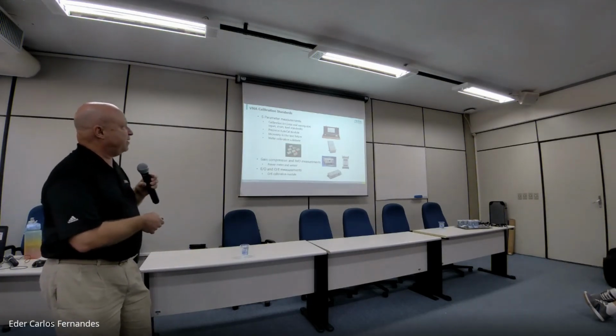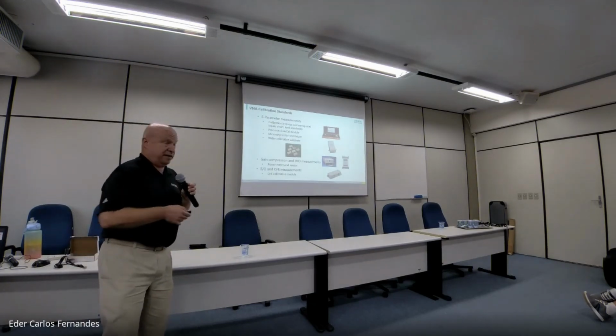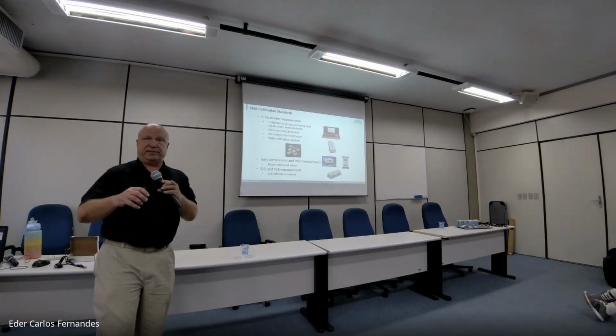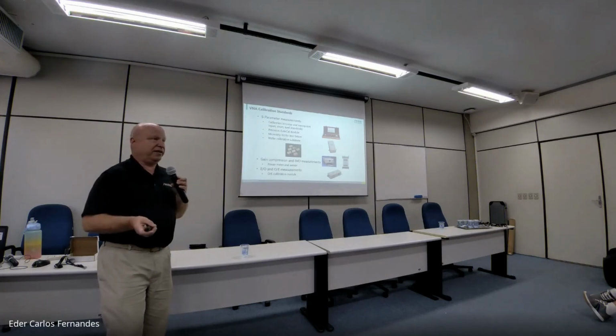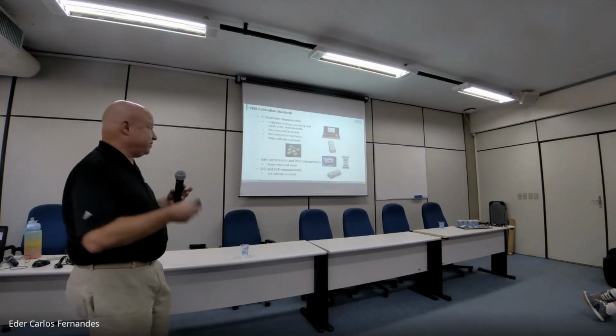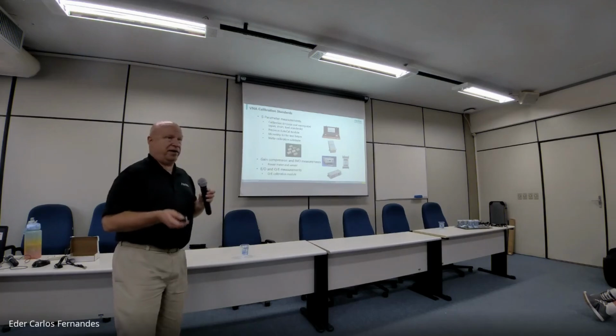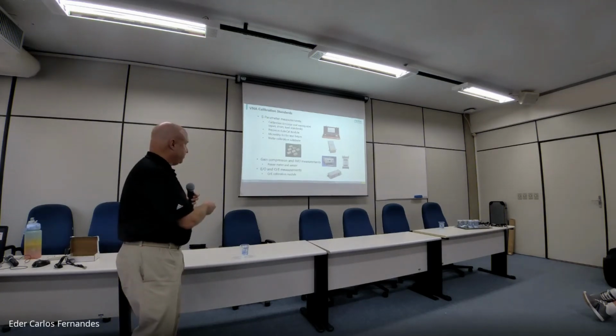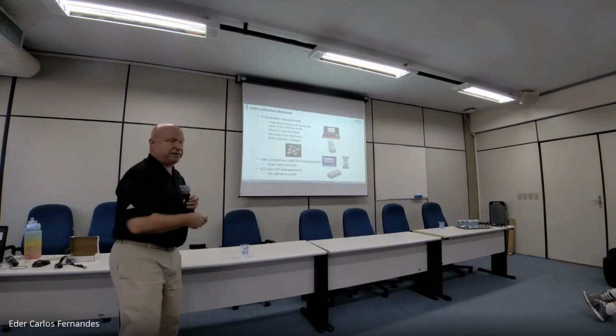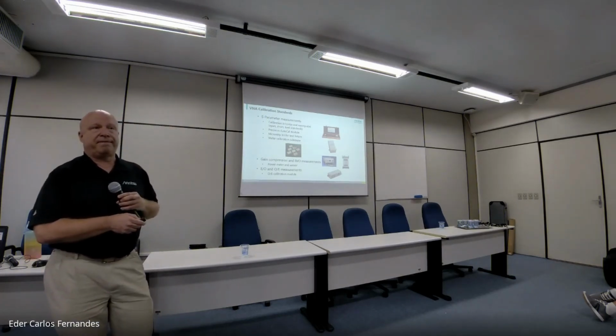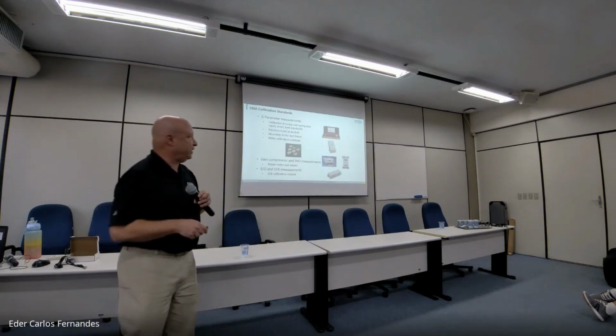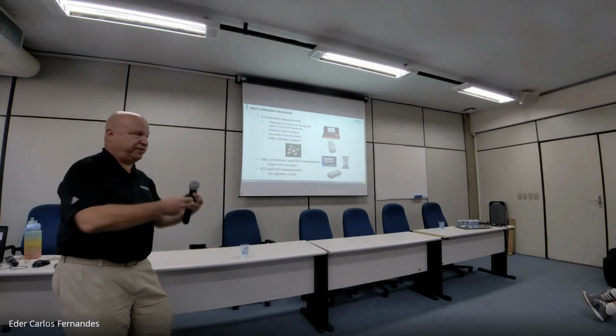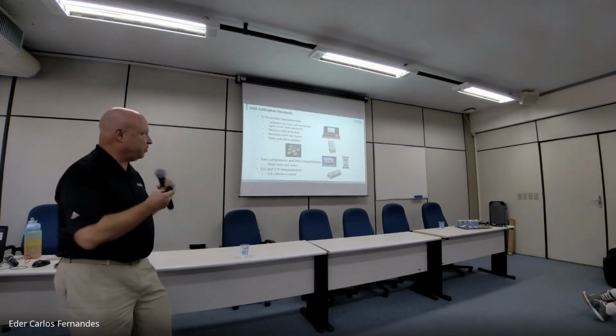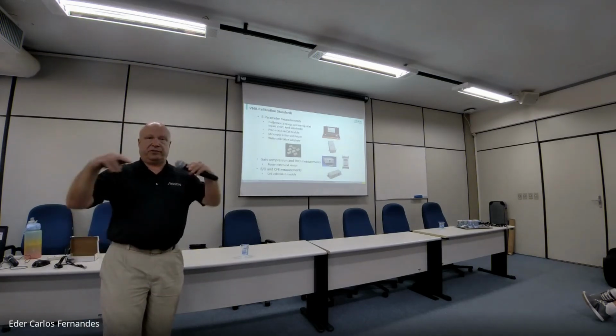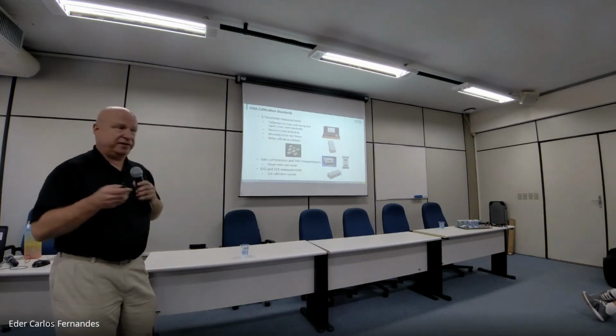We have microstrip cal kits. You can see these kinds of substrates that fit into a fixture. So if we're doing measurements where there are no connectors, it's just a substrate and I have a specific fixture to use, or on wafer. On wafer also makes use of substrates that have the same standards that are here, but etched onto the substrate. And so we touch down on the various standards to complete our calibration, whether it's in a fixture with some jaw mechanism or on a probe station with real probes. And we'll talk more about probing in a little while.